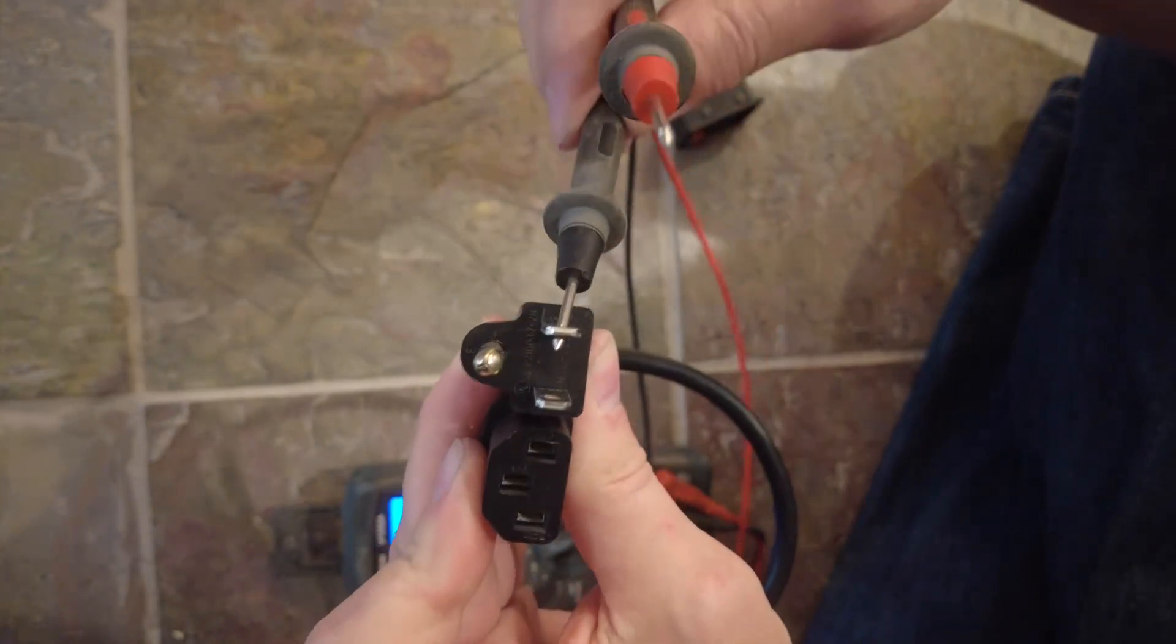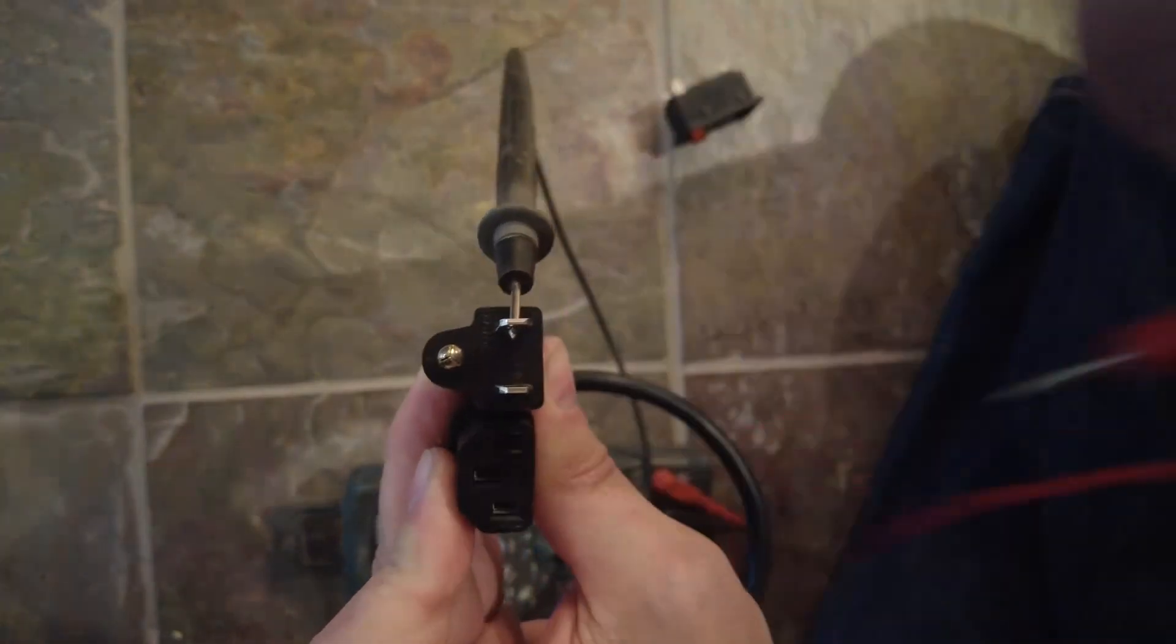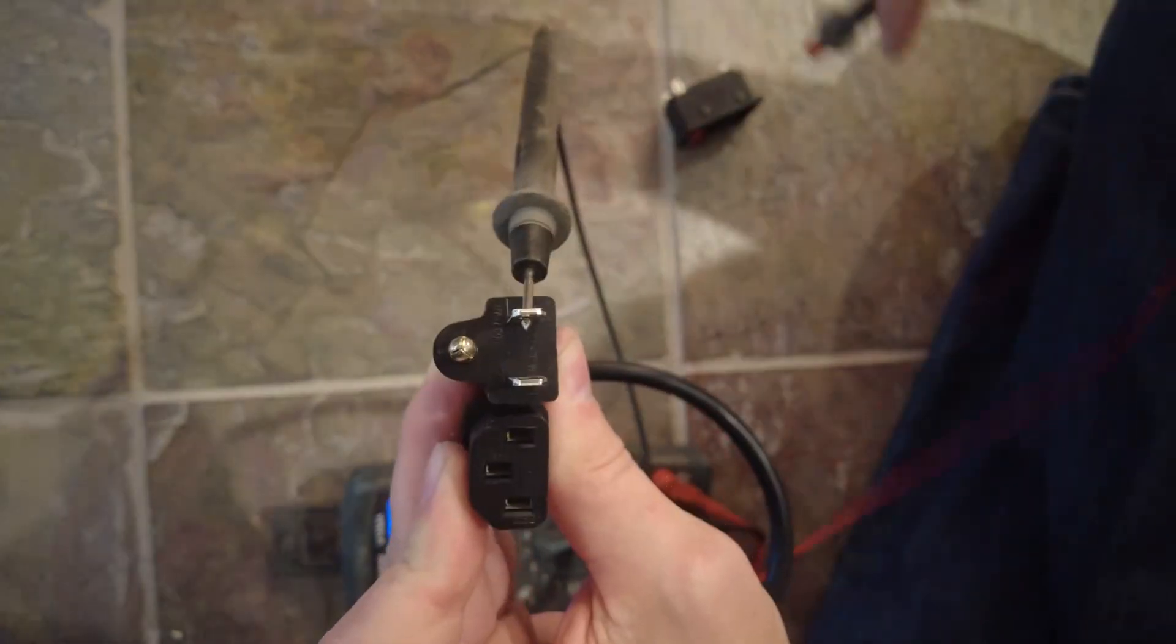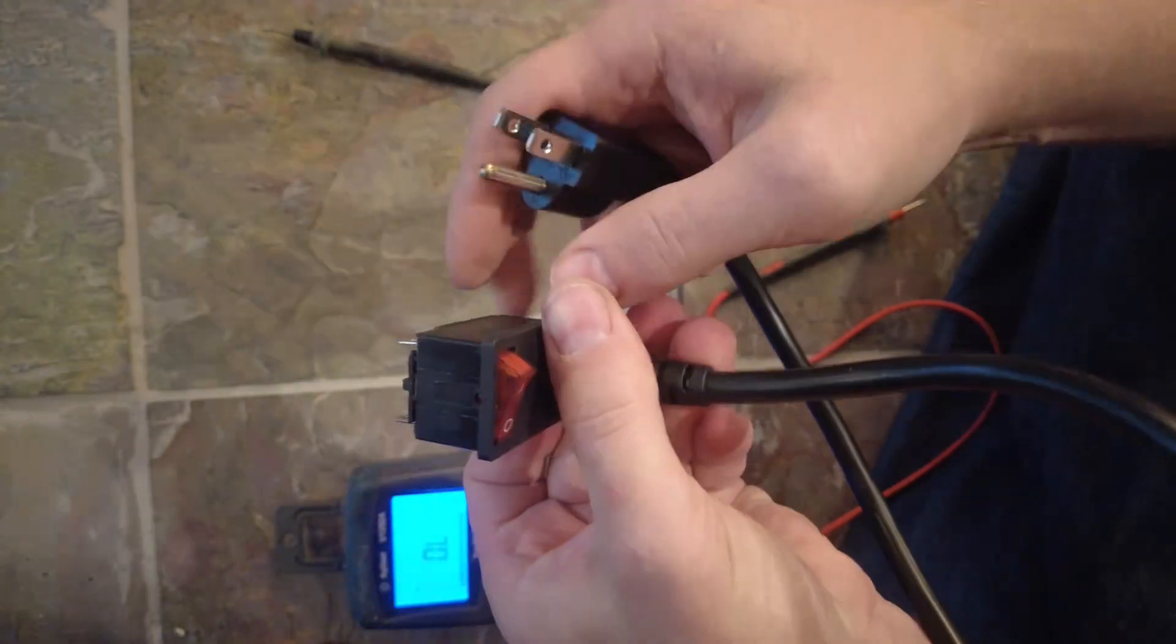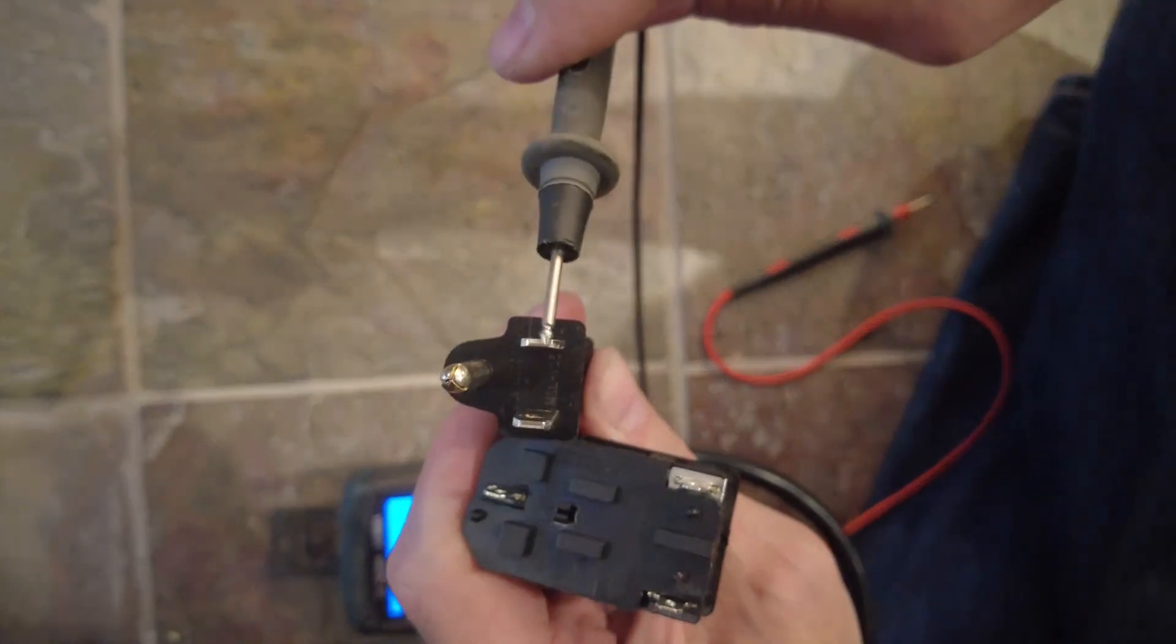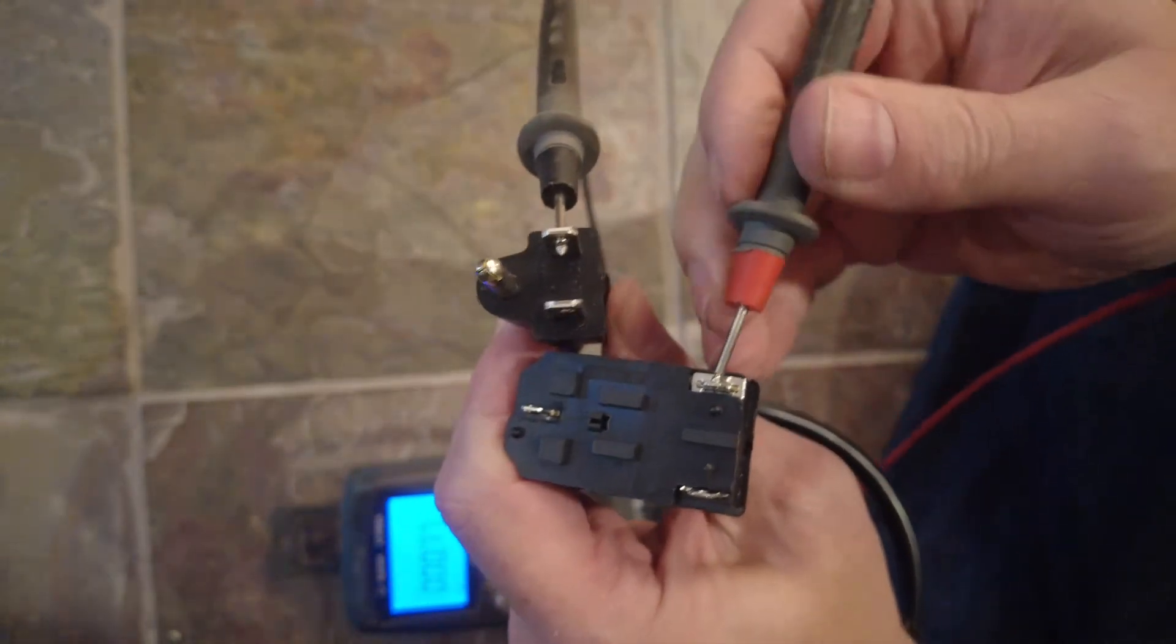We can prove that by doing a little continuity test. This should be the line, the 120 volts. We've got nothing here. And we got it here. The line. Nothing here. Nothing here. Now if I plug this in here, turn this on, we'll put this on the line side again, and we'll find it. Okay, there it is.